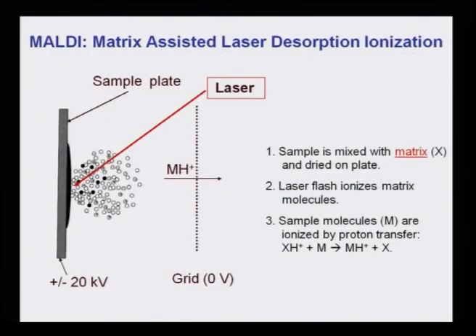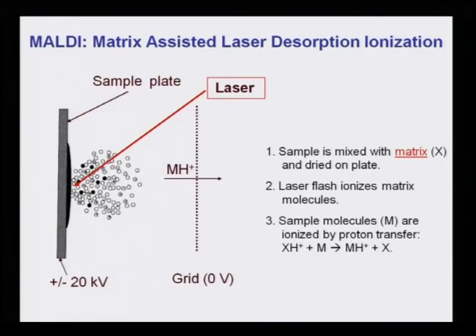In electrospray ionization, the sample is introduced with nitrogen gas through a nozzle with a very high voltage applied, forming charged droplets. For MALDI, the laser beam of 337 nanometers reacts on the cyano-cinnamic acid surface — the sample is mixed with the matrix, dried on a sample plate, and laser flash ionizes the matrix molecules; sample molecules are then ionized by proton transfer. Both MALDI and ESI are soft methods used for peptides and proteins which get denatured easily with hard methods.